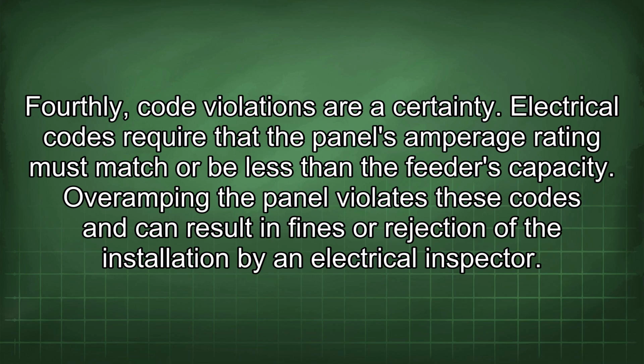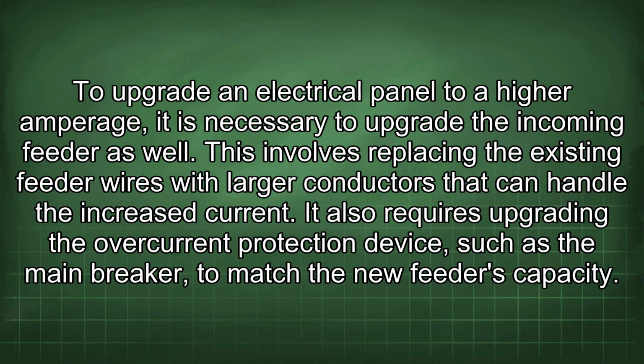Fourthly, code violations are a certainty. The electrical codes require that the panel's amperage rating must match or be less than the feeder's capacity. Overamping the panel violates these codes and can result in fines or rejection of the installation by an electrical inspector. To upgrade an electrical panel to a higher amperage, it is necessary to upgrade the incoming feeder as well. This involves replacing the existing feeder wires with larger conductors that can handle the increased current. It also requires upgrading the overcurrent protection device, such as the main breaker, to match the new feeder's capacity.